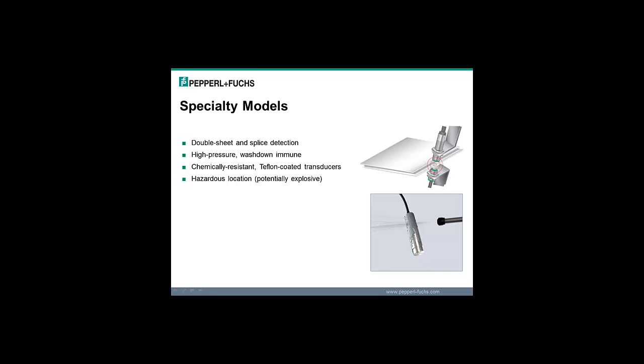So we've kind of gone over the basic models of switch point, analog output, cylindrical housings, and surface mount housings. But there's a lot of other technologies and capabilities for ultrasonic sensors than just those simple rudimentary designs. One is double sheet detection. So if you're in a paper feeding application, you want to know if there's a misfeed where two pieces of paper get fed through. You can do that with a special ultrasonic Thru-Beam model. Likewise, on a big paper roll, if there's a splice, you need to detect that splice and cut it out so it doesn't go into your finished product.